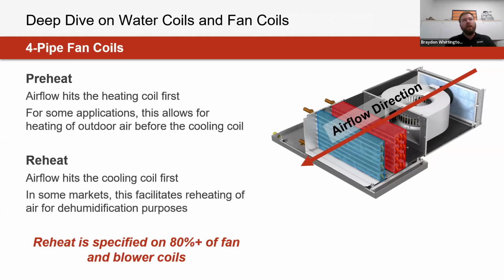So for example, on screen here, a preheat condition is having the heating coil before the cooling coil. Beneficial for this is for handling any outdoor air that might be going through this product. So effective strategy when dealing with lower entering air temperatures. And for reheat configurations, this can be very beneficial if you're running both of these coils when looking at dehumidification within the product there as well. So what we see more commonly than not, 80% of what we see for firms that deal with 4-pipe applications are configuring them for a reheat configuration.